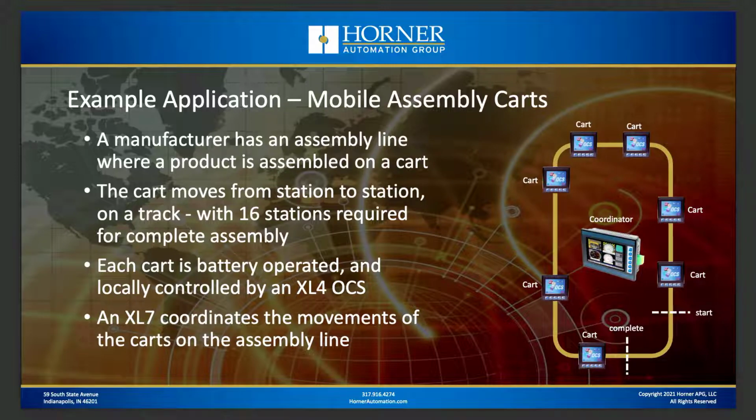Now, what if we used Modbus TCP here? Well, the XL7 that's communicating with all the XL4s, with all the carts, would have to talk to them in a round-robin fashion. It would have to poll one at a time to get information, and when it was ready to write information, it would need to interrupt its poll and go write information. That might take several seconds to actually happen.